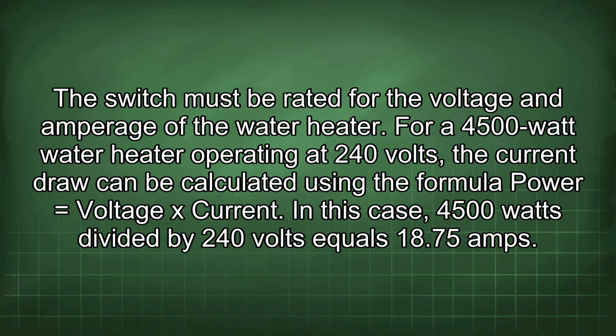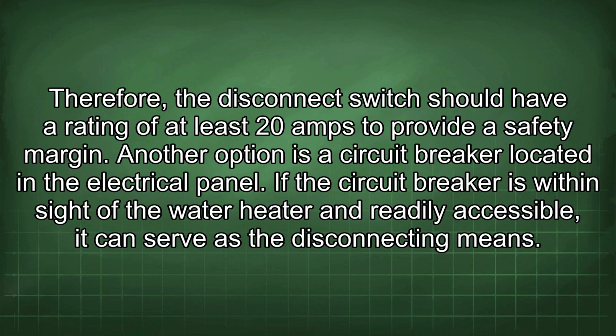For a 4,500-watt water heater operating at 240 volts, the current draw can be calculated using the formula power equals voltage x current. In this case, 4,500 watts divided by 240 volts equals 18.75 amps. Therefore, the disconnect switch should have a rating of at least 20 amps to provide a safety margin.